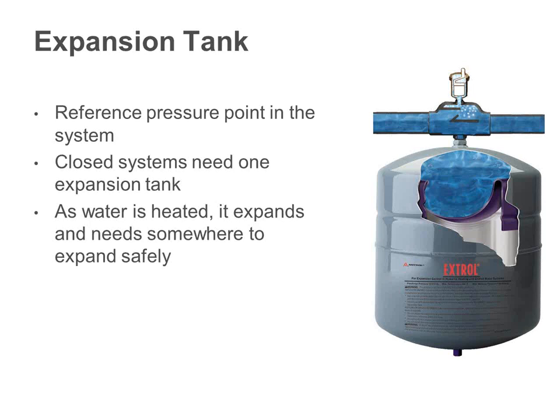As we heat water, it expands. If we didn't give it anywhere to go, it would come out the relief valve. Water coming out the relief valve is not a good thing. We don't want to add fresh water to a boiler system. It's the worst thing you can do. So basically, what the expansion tank does is provide you a cushion of air. In the expansion tank you're looking at here, there's a diaphragm in it. That's a purple bladder or rubber piece in there.